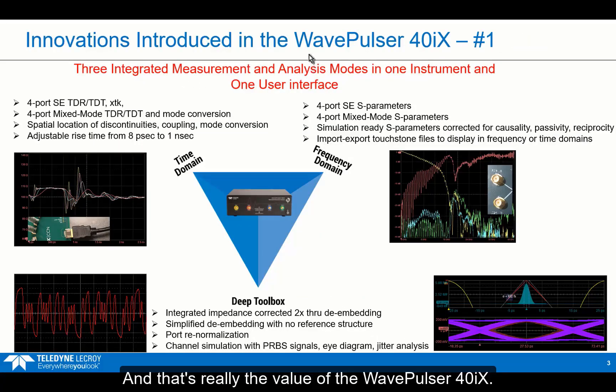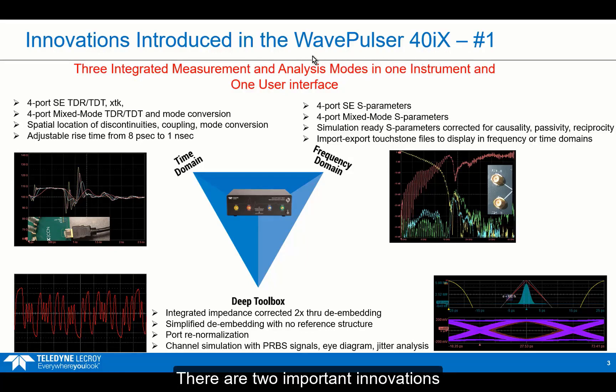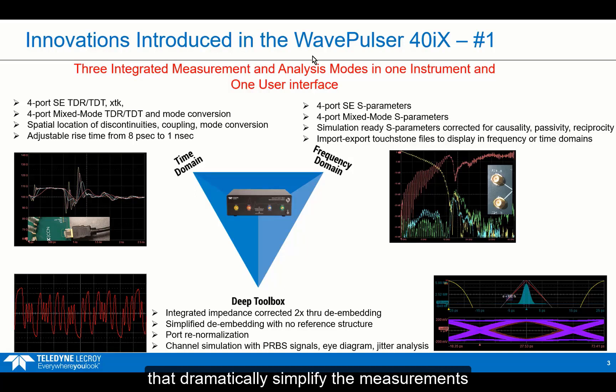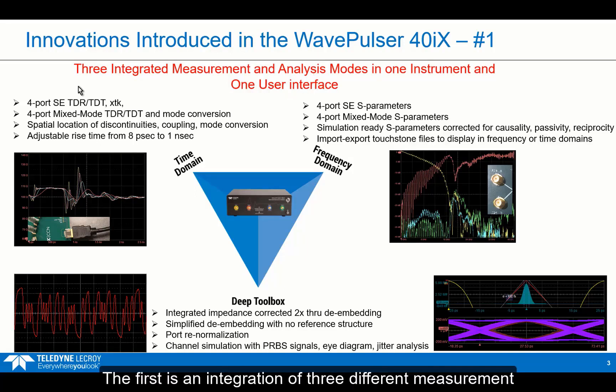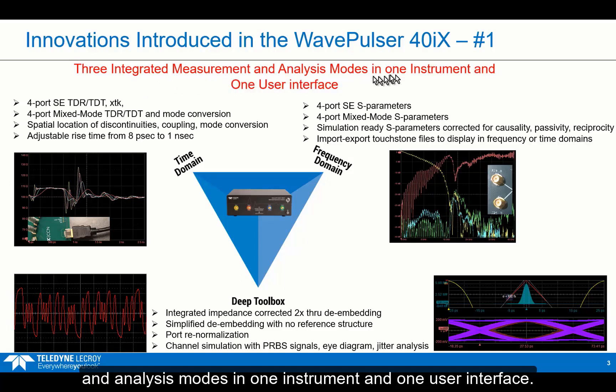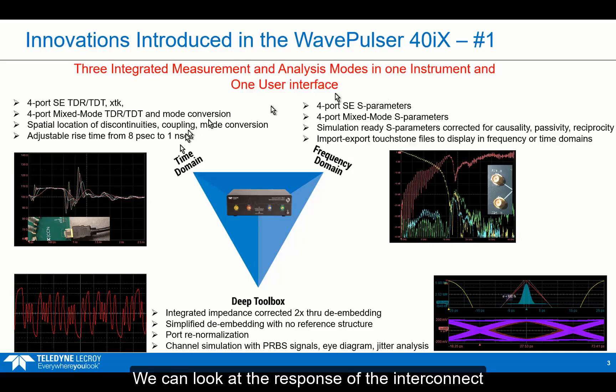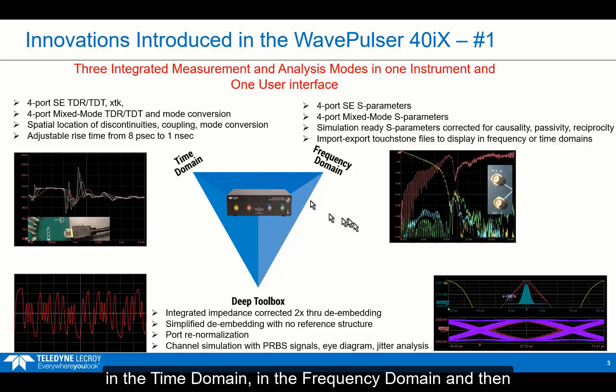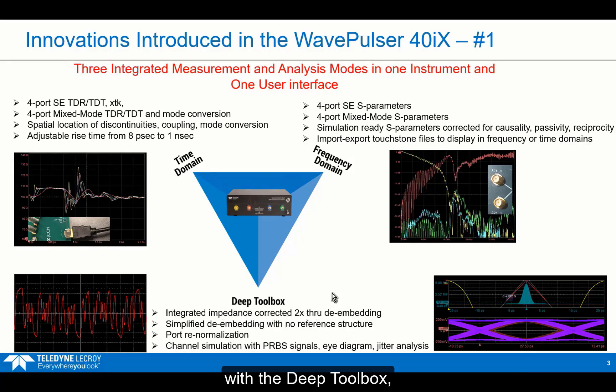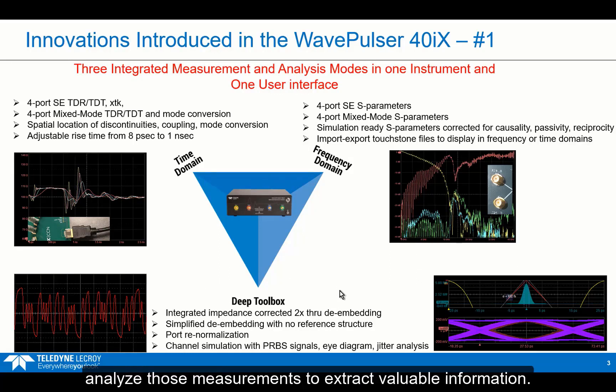And that's really the value of the WavePulser 40iX. There are two important innovations introduced in this instrument that dramatically simplify the measurements and analysis. The first is an integration of three different measurement and analysis modes in one instrument and one user interface. We can look at the response of the interconnect in the time domain, in the frequency domain, and then with a deep toolbox, analyze those measurements to extract valuable information.